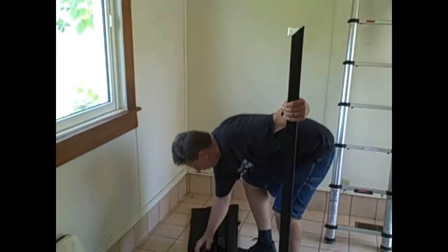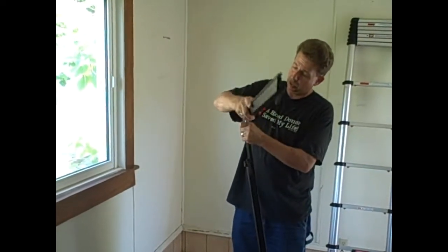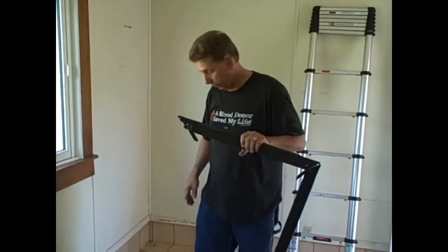We're getting up in the attic of the front part of this house. It appears it has knob and tube wiring in it, so we're going to go up and see if it's live. Hopefully it isn't because on my brief walkthrough when I made the offer, I didn't see this knob and tube. I've got my meter and my camera and we're headed up there. And it is live knob and tube. We'll set up the blower door and do a test on the building to see how tight it is and check efficiency with all the data from the furnaces.